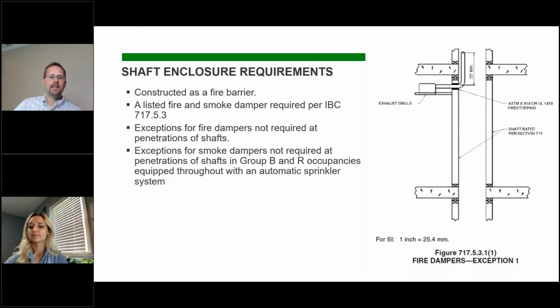Anytime you have a shaft, you need a fire smoke damper per the IBC. And there are some exceptions for that, and we're not going to talk about all the exceptions. A lot of them are the standard ones we've already discussed with UL enclosures and assemblies and stuff like that. But in general, you're supposed to have a fire smoke damper, and there are some exceptions where you can just bring it down to a fire damper. But the one exception I wanted to discuss is the exception that allows for steel subducts.